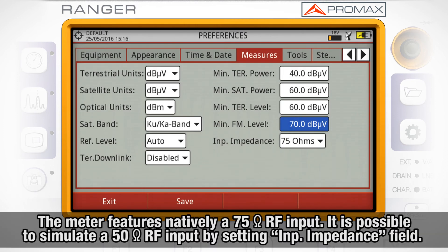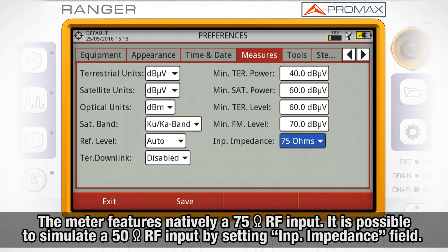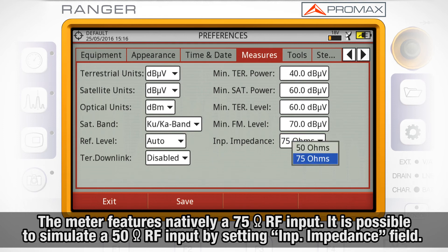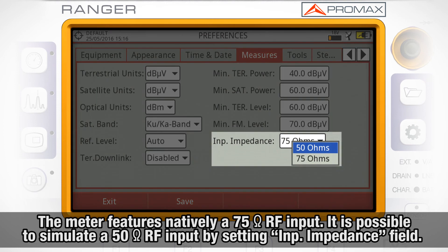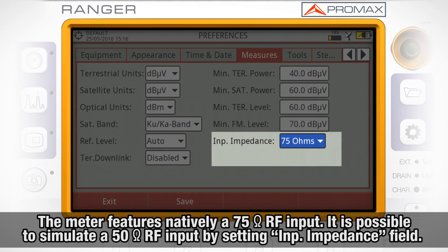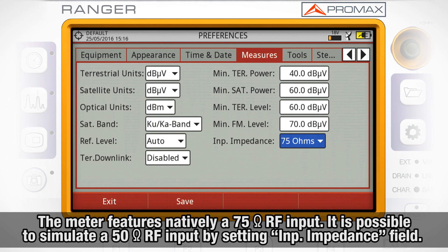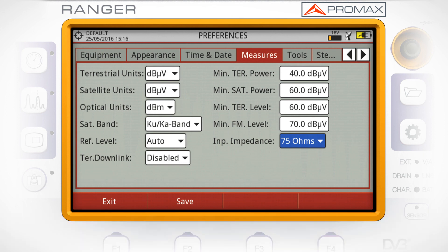The meter features natively a 75 ohm RF input. However, it is possible for the meter to take measurements simulating a 50 ohm RF input. This can be set in the input impedance field.